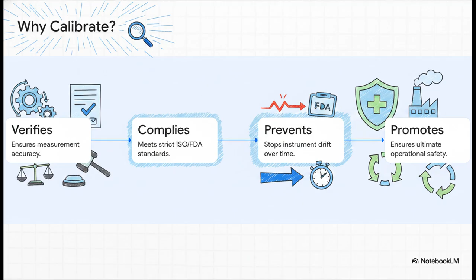The benefits of doing this are immense. We've condensed the main reasons into this high-impact checklist. Regular calibration verifies measurement accuracy, for sure, but it also ensures compliance with incredibly strict ISO and FDA regulations, which keeps companies out of massive legal trouble. It detects and prevents the instrument drift we talked about earlier. And, most importantly, it promotes ultimate safety by preventing large-scale production defects from ever reaching the public.